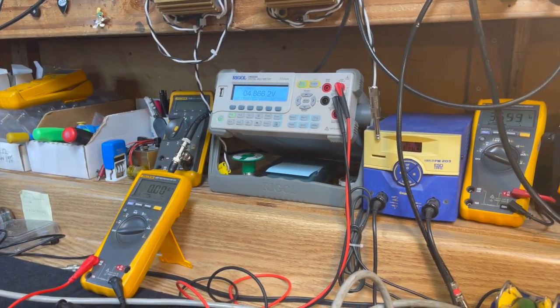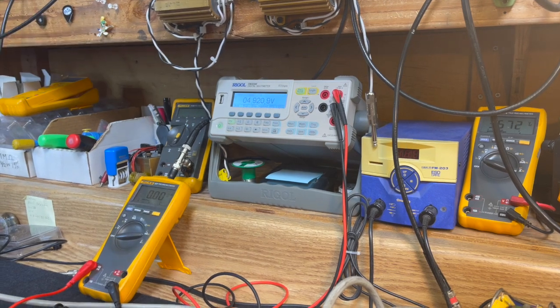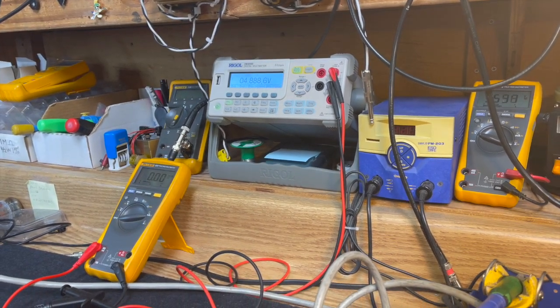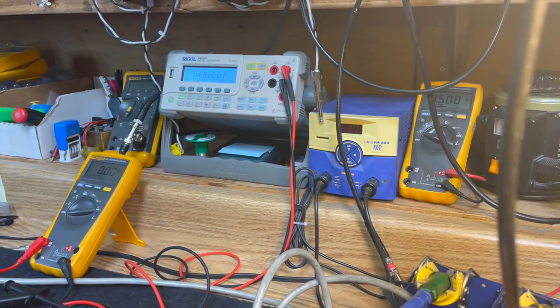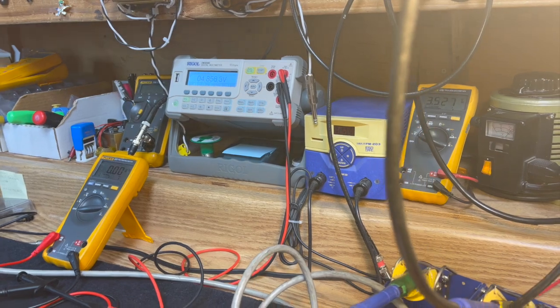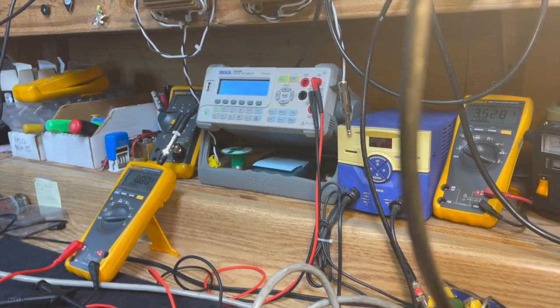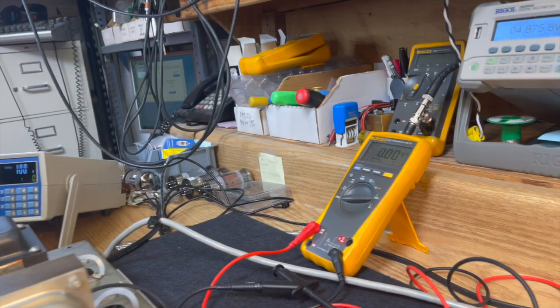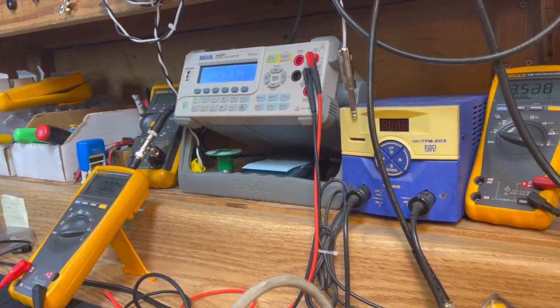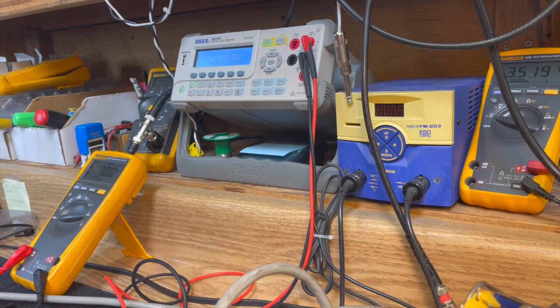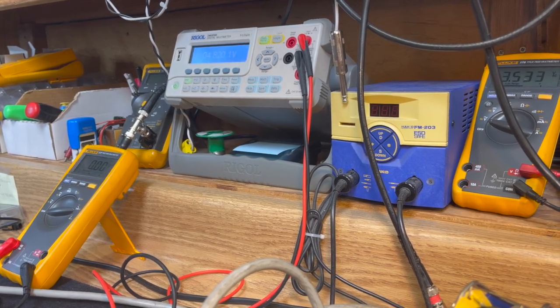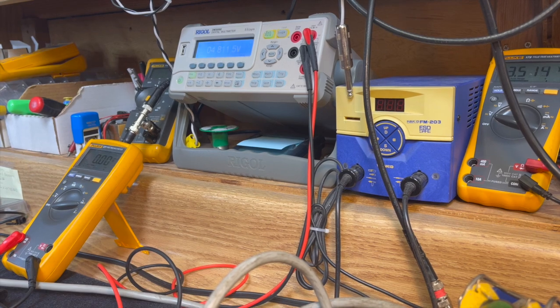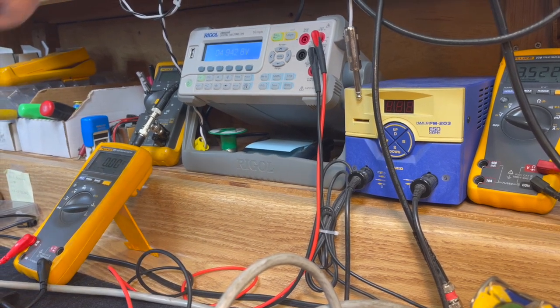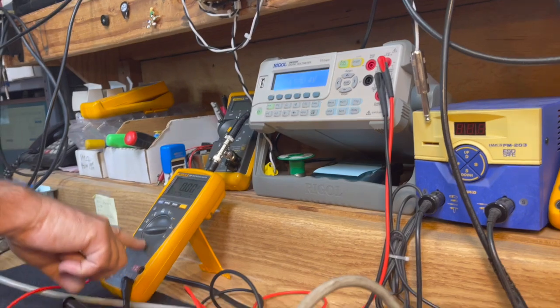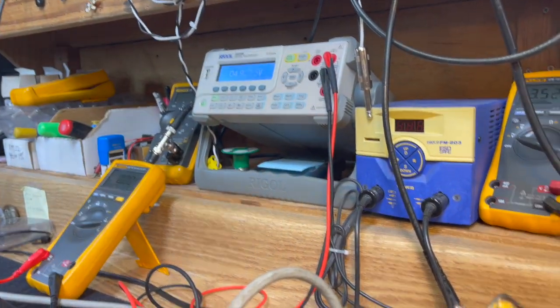Zero current, a little residual DC voltage that these two caps are seeing, because there's 3.5 AC volts going into the power supply. So it looks like we are getting voltage through, but not enough current to read anything. Now we're going to bring the voltage up very slowly, and monitor the AC volts, the DC volts, and the current meter to see if there's any changes.